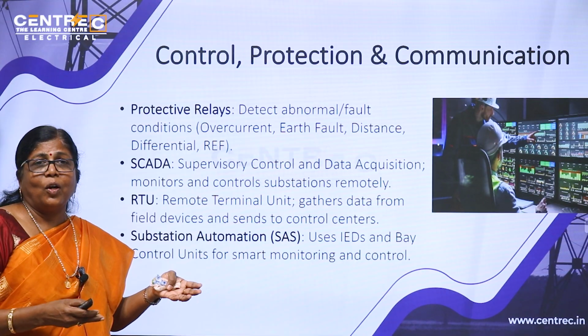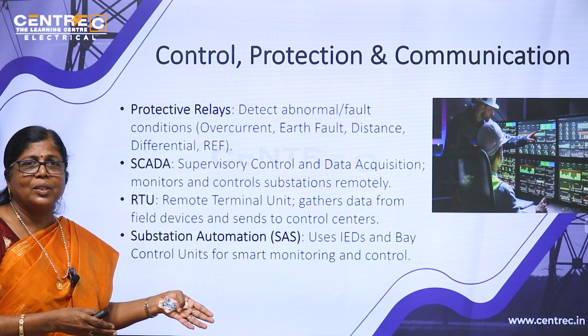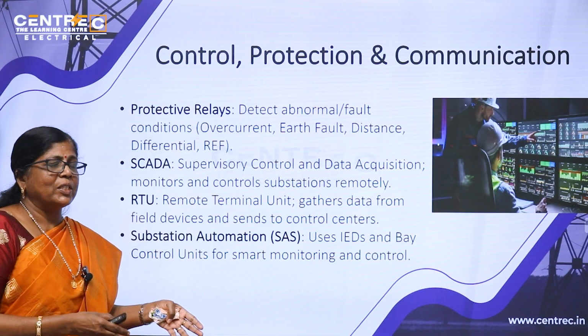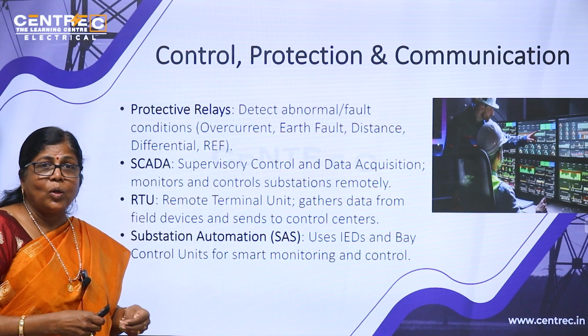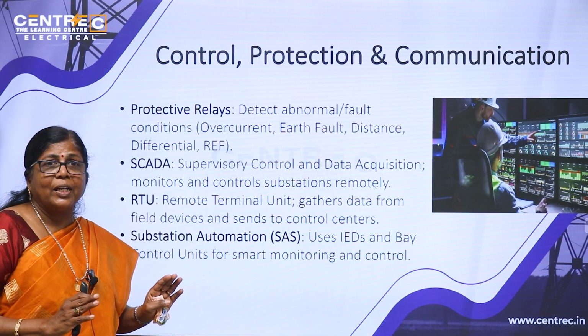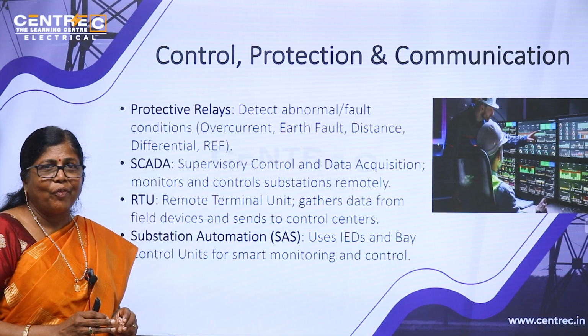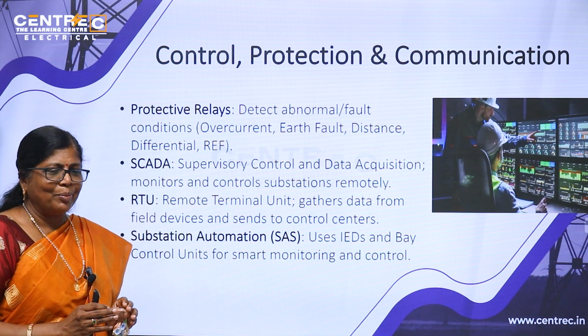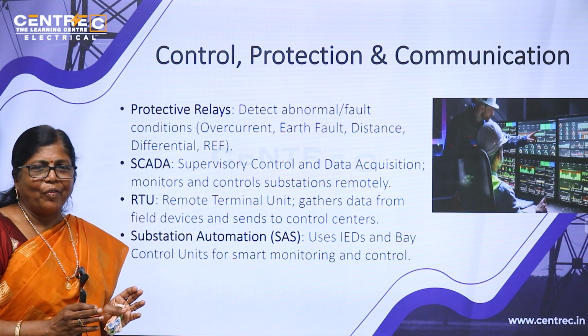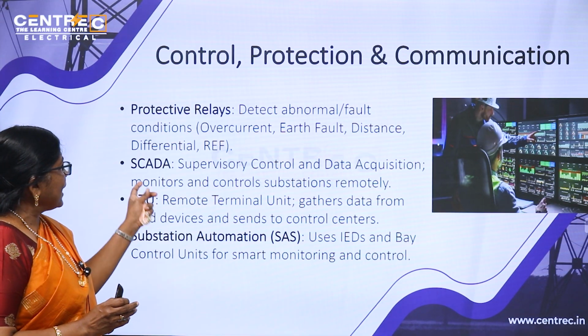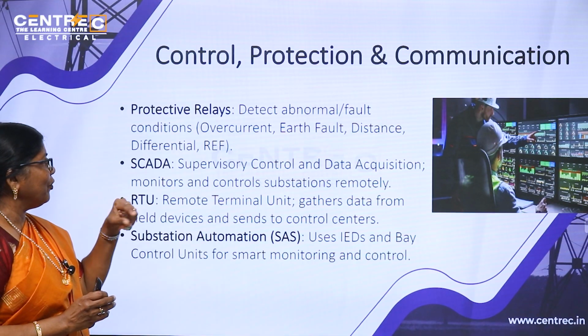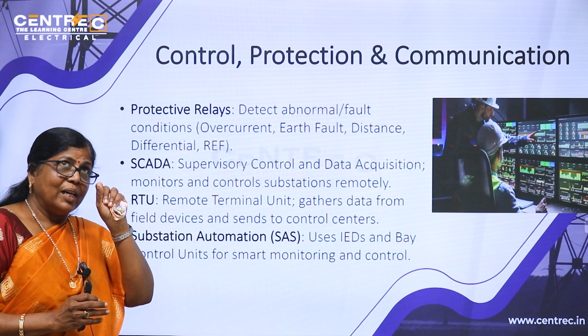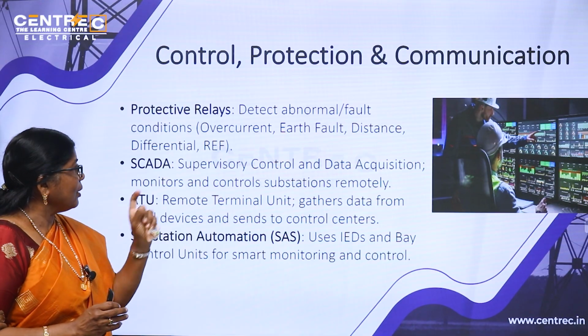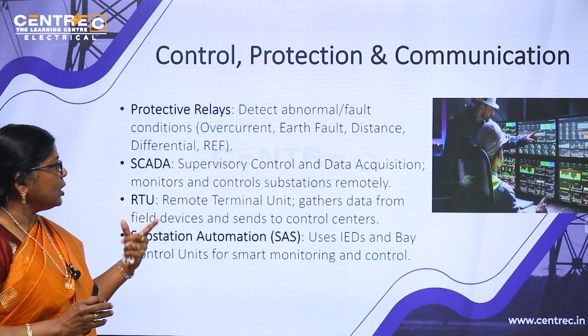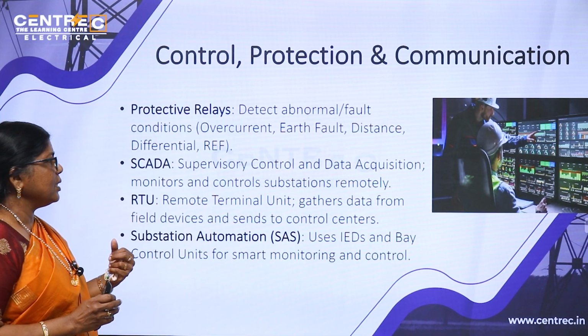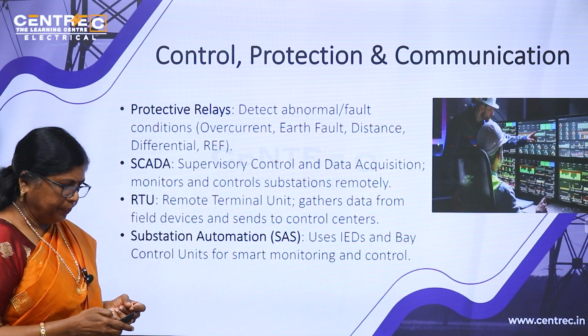But the operators handling the control room in Moolamattom power station are not able to increase all the machines together to the full 780 megawatt, because it is a risk factor. If it is increased beyond 780, that is a risk factor in peak time. So SCADA itself can understand how much power is left in that station. A remote terminal unit also gathers this data from field devices and sends it to control centers.